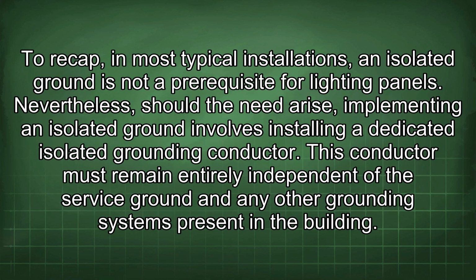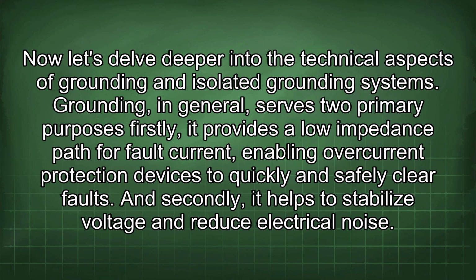To recap, in most typical installations, an isolated ground is not a prerequisite for lighting panels. Nevertheless, should the need arise, implementing an isolated ground involves installing a dedicated isolated grounding conductor. This conductor must remain entirely independent of the service ground and any other grounding systems present in the building. Now let's delve deeper into the technical aspects of grounding and isolated grounding systems. Grounding, in general, serves two primary purposes. Firstly, it provides a low impedance path for fault current, enabling overcurrent protection devices to quickly and safely clear faults. And secondly, it helps to stabilize voltage and reduce electrical noise.